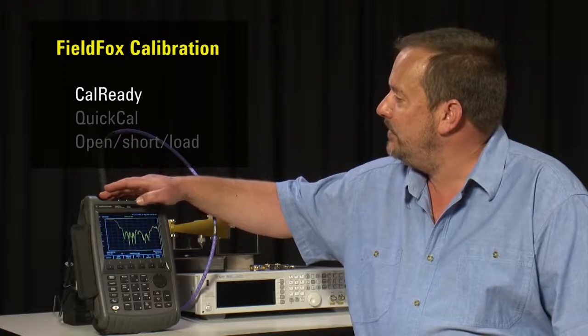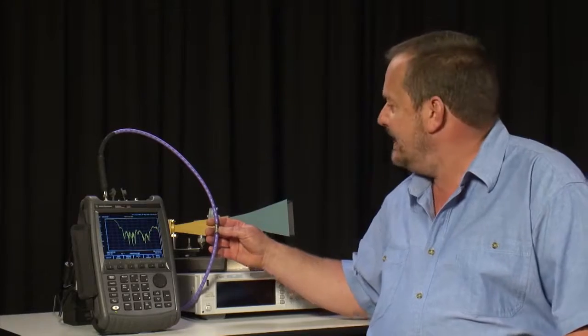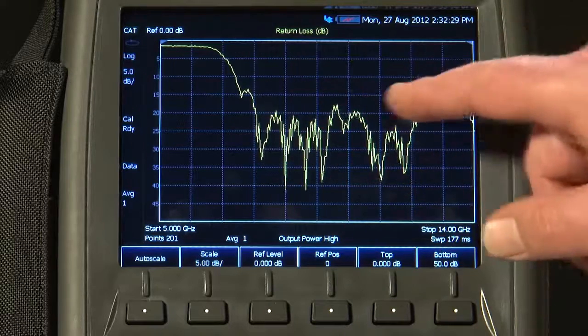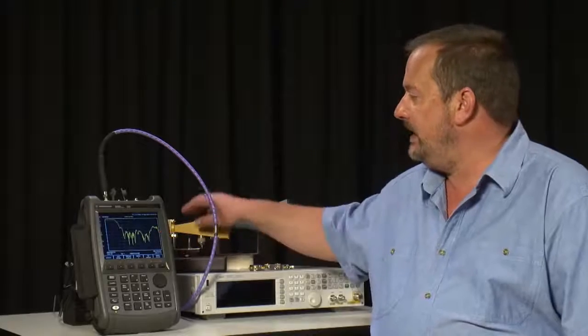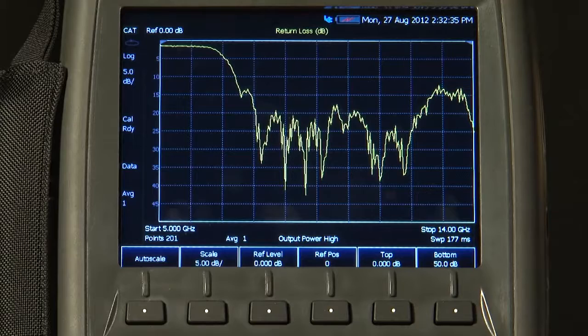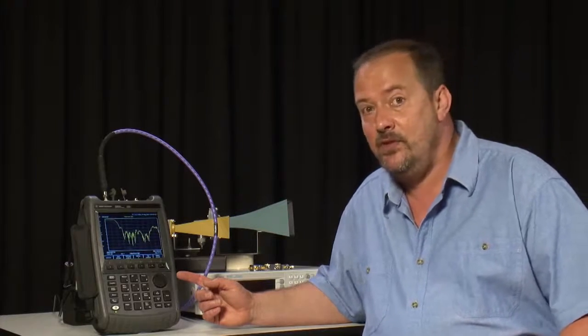So provided we are happy that we are going to be measuring here the response of both this cable, which is a very good quality low loss cable and quite short, and this antenna, so the display of return loss is showing as the return loss of both the antenna and the cable, then we do not need to do any calibration at all. And this may be perfectly acceptable for factory acceptance testing before you go out on site.